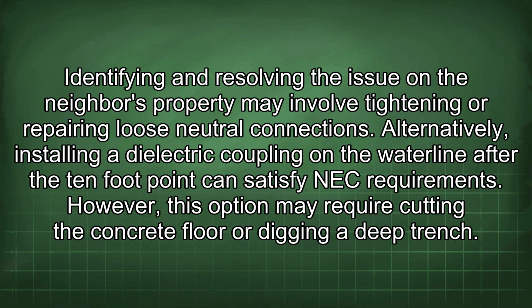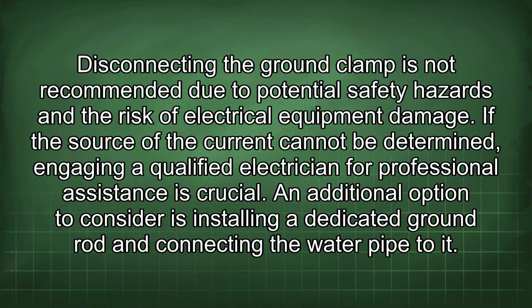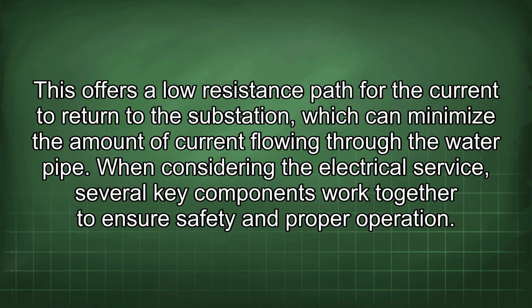However, this option may require cutting the concrete floor or digging a deep trench. Disconnecting the ground clamp is not recommended due to potential safety hazards and the risk of electrical equipment damage. If the source of the current cannot be determined, engaging a qualified electrician for professional assistance is crucial. An additional option to consider is installing a dedicated ground rod and connecting the water pipe to it. This offers a low resistance path for the current to return to the substation, which can minimize the amount of current flowing through the water pipe.